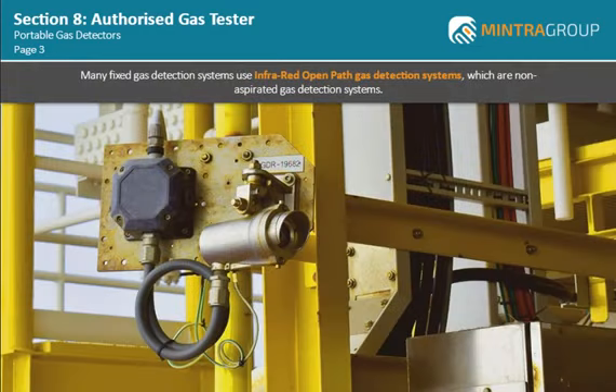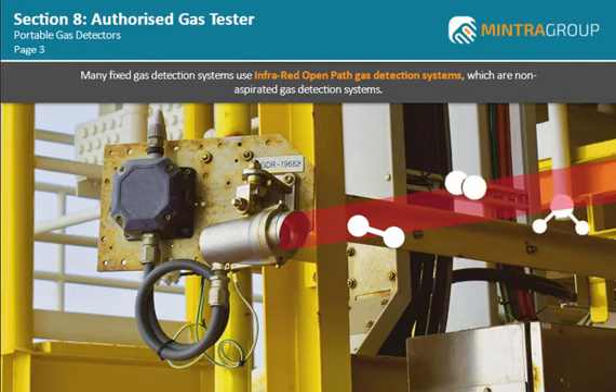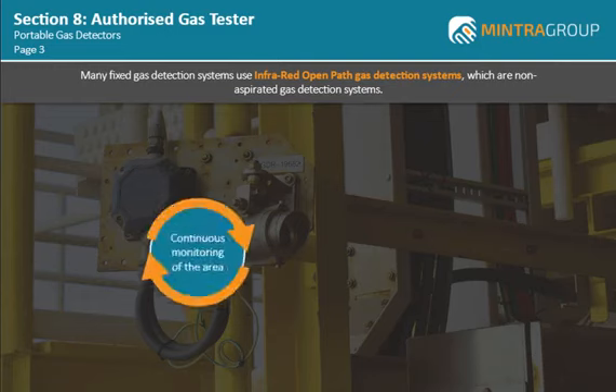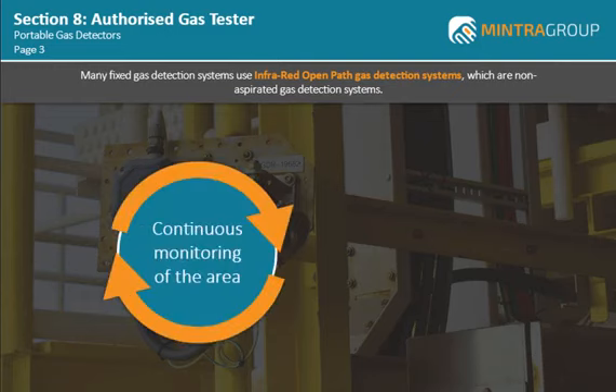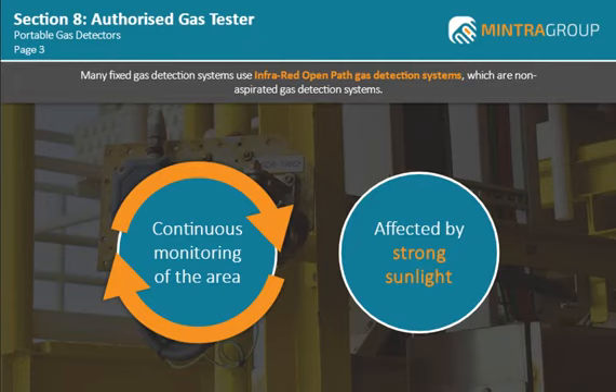Many fixed gas detection systems use infrared open path gas detection systems, which are non-aspirated gas detection systems. The gas detectors send out a beam of infrared light, detecting gas anywhere along the path of the beam. Usually, there are separate transmitter and receiver units at either end of a straight beam path. The strengths of this type of gas detection include continuous monitoring of the area. However, the detector can be affected by strong sunlight, which can confuse the analysis and cause spurious alarms.